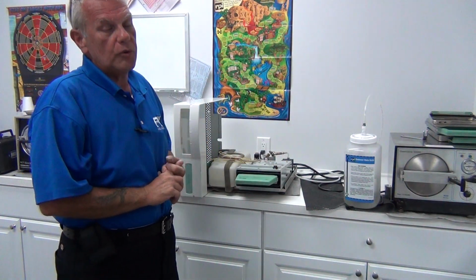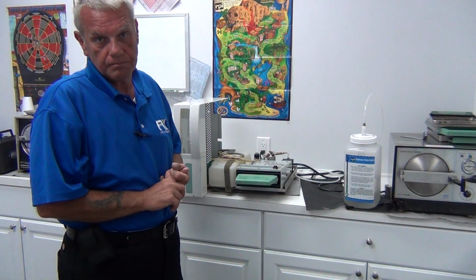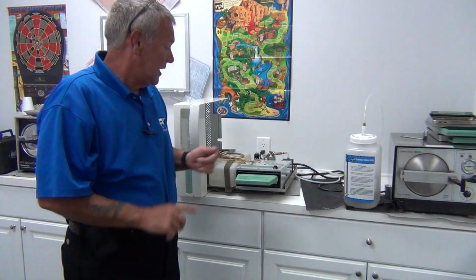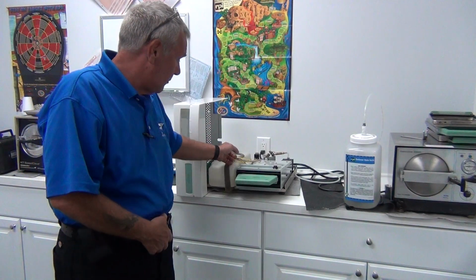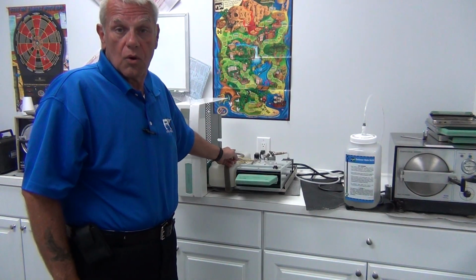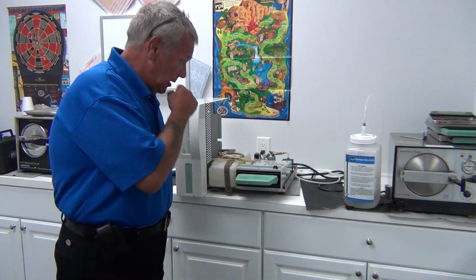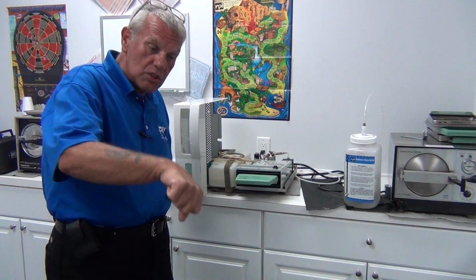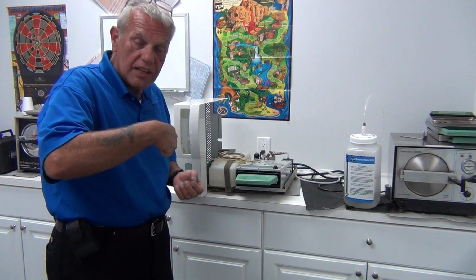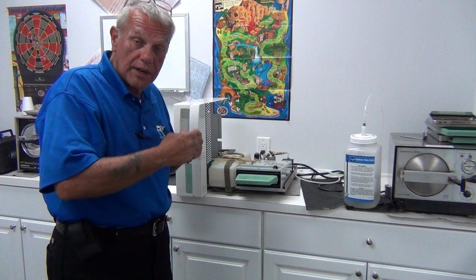If you do not use steam distilled water, it will error out immediately. It will tell you exactly what's happened. If you do mess up and somebody has put tap water in it, or a less than quality water, put the cover back on the machine, carry the machine into the doctor's operatory, use his big suction or his saliva ejector, suction out the reservoir, and then replace it with distilled water. You'll get a good code on it and it will work that time.